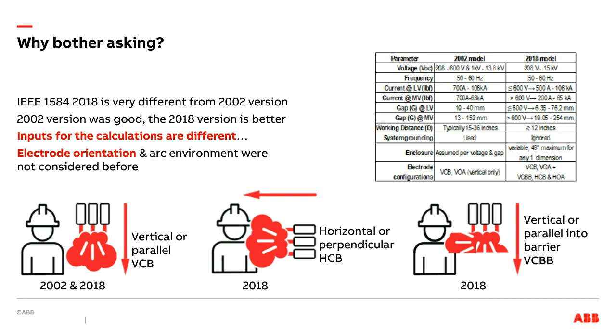So to simplify the example, I'm using this analogy: those two conditions are fairly different from what the previous standard was. As far as voltage, gaps, even enclosure, the new method is very similar. Enclosure is a variable for energy, not for arcing current. The gap now allows for more continuous measurement of the gap. So if you previously used a certain value and now you want to use a 10% larger value for whatever reason, you can, and it will have an impact.